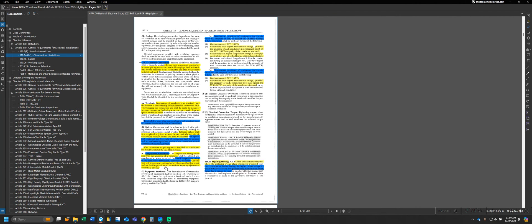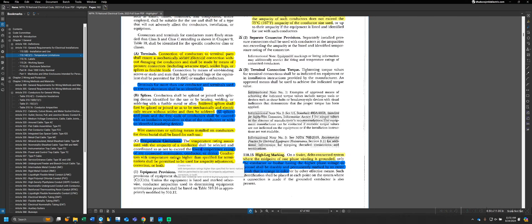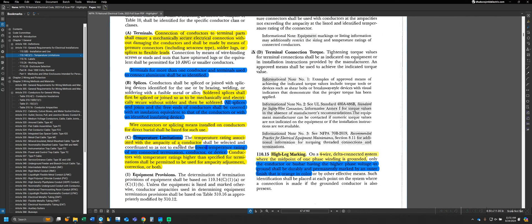Going back to our section, the NEC is telling you that when selecting the ampacity of a conductor, it has to be coordinated such that the ampacity temperature rating does not exceed the lowest connected device. In addition to conductors, other items used in the electrical industry also have temperature ratings — such as breakers, switches, receptacles, lugs in a panel, and other items.